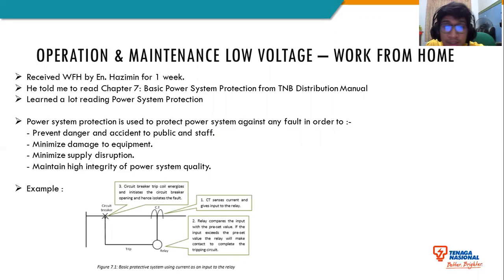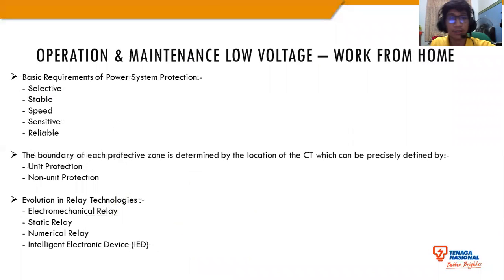The current transformer senses current and gives input to the relay. The relay compares the input with the preset value. If the input exceeds the preset value, the relay will make the contact to complete the tripping circuit. Then the circuit breaker trip coil energizes and initiates the circuit breaker opening, hence isolating the fault. So the component will not be damaged.